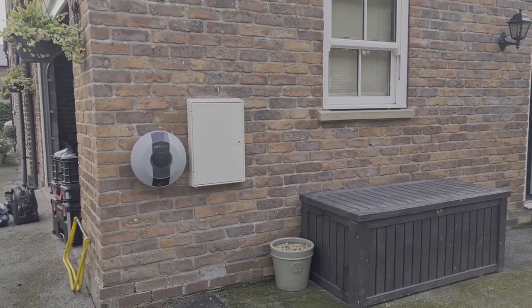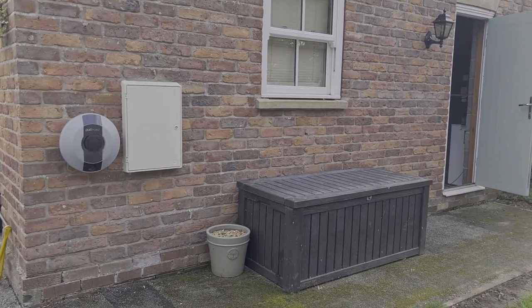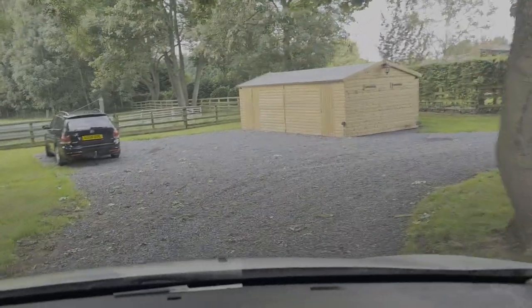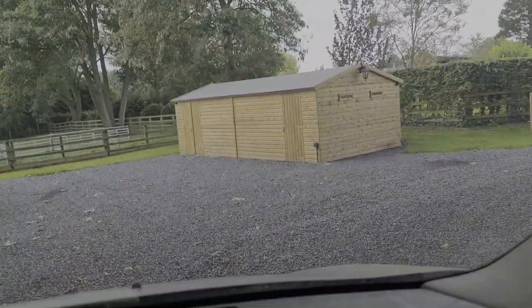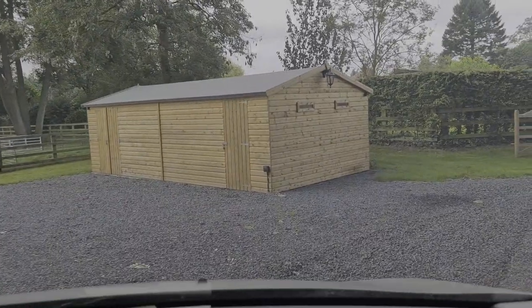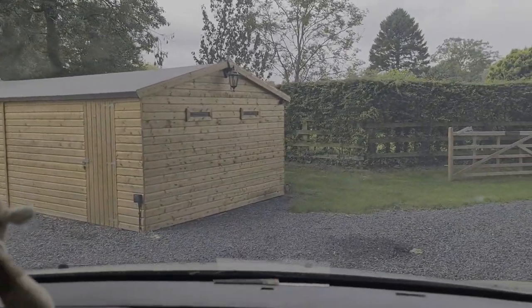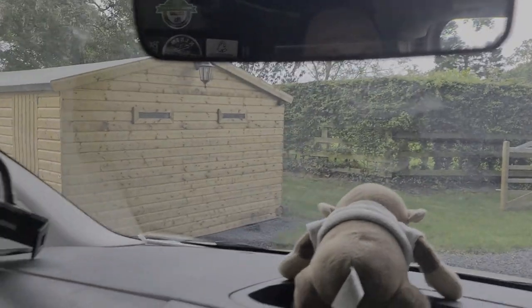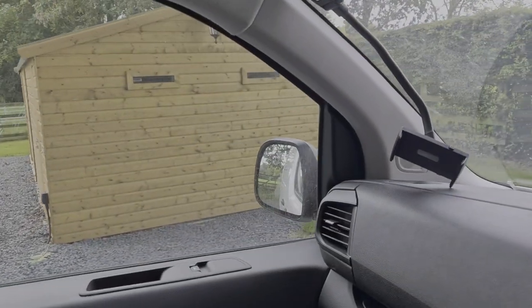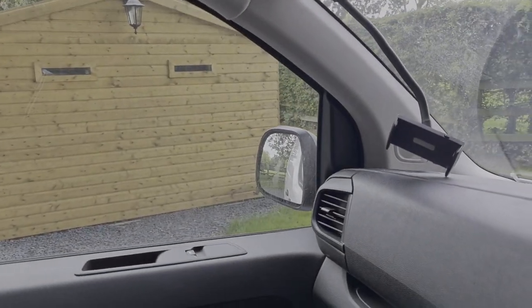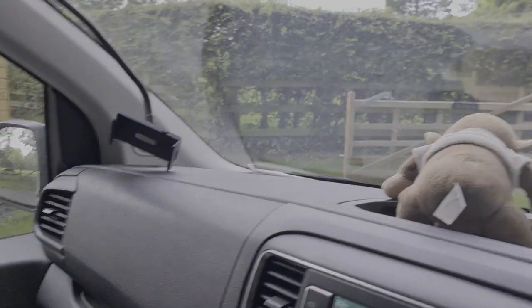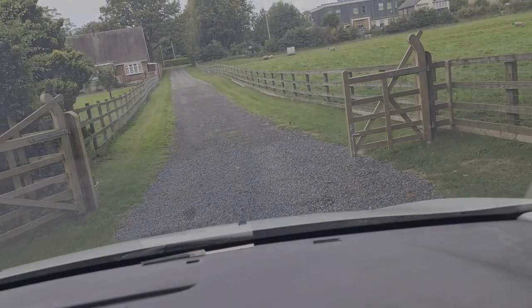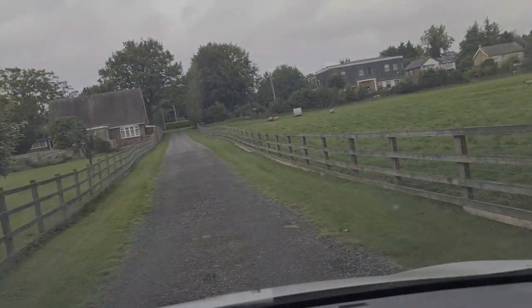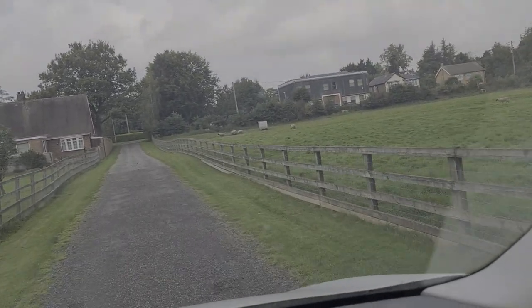So we do actually have some supplementary earth on this install. If you see here as well, there is also this workshop building, and this is on earth foundations as well, so there's electrodes on this building, and that goes back in a 16mm steel wire armor cable to the main consumer unit. So while we haven't put an earth rod in especially for the hot tub, there are numerous points of earthing within this installation.